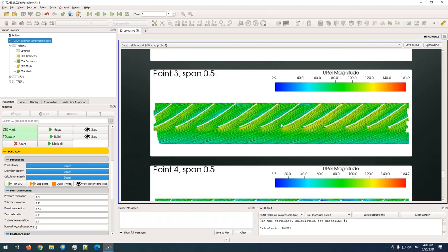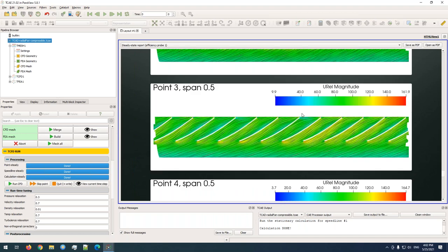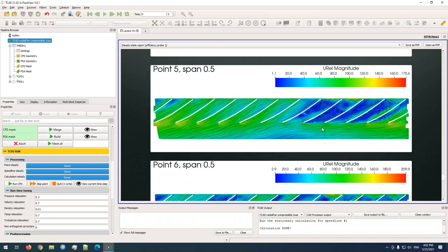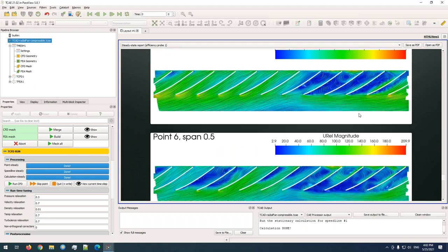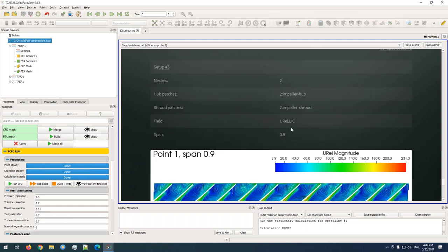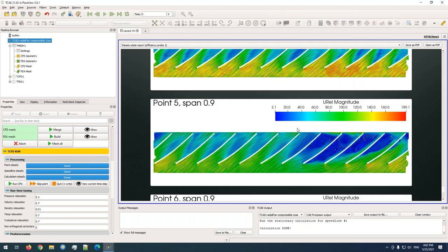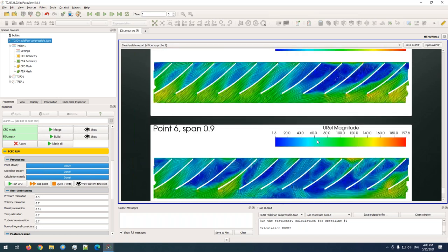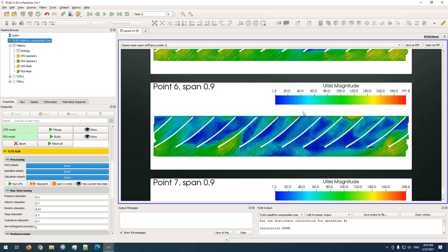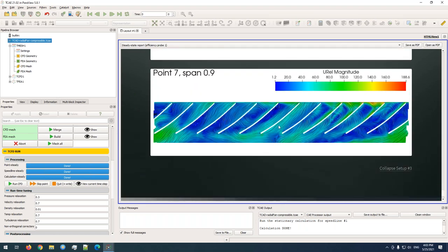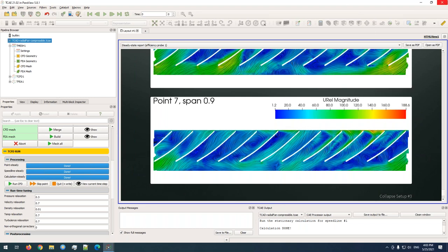So again, you can see what is happening near the tongue area, let's say, and for which point the recirculation occurs and how the recirculation is expanding, for example. So it's a pretty nice view for the first sight analysis, what is happening where, and possibly where some modification of the geometry should be placed or should be focused on.